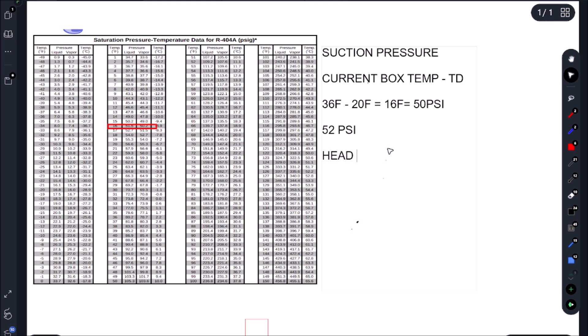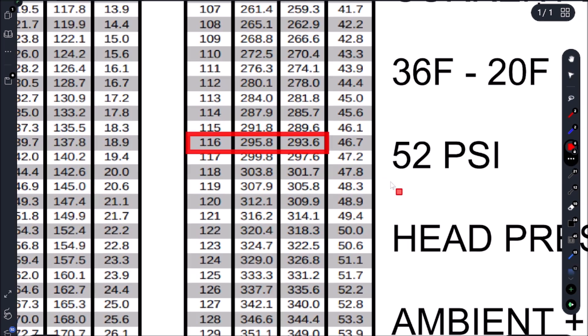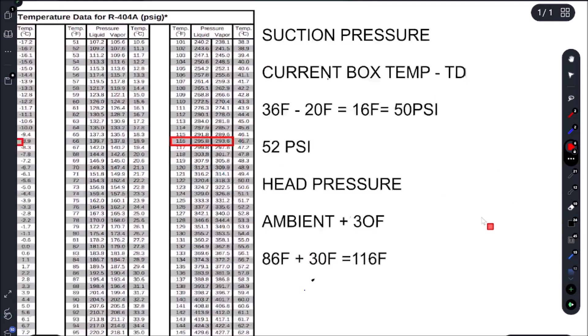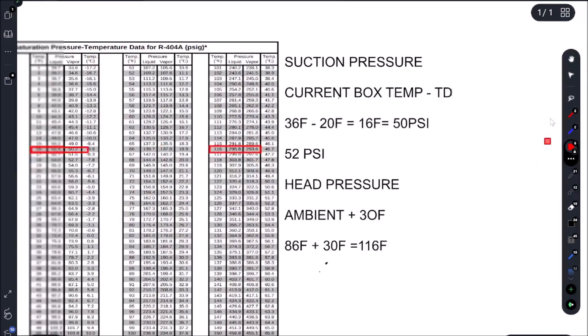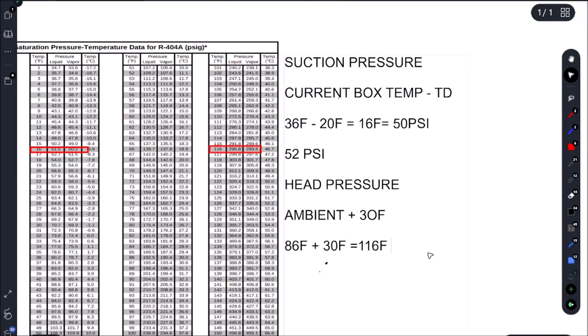Now for our head pressure. Once again it's ambient plus our split, which in this case is 30 Fahrenheit. So it was 86 Fahrenheit, and then we add in our condenser split, which gives us 116 Fahrenheit. And that puts us at 295 PSI. And we ended up having exactly 295 PSI. So pressures are adding up correctly. The unit's cooling very quickly. So we are all good on this one.